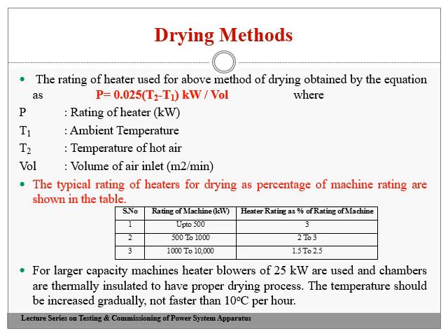Therefore, P equals 0.025 into (T2 minus T1) kilowatt per unit volume, where P is the rating of the heater in kilowatts, T1 is the ambient temperature where you are going to do the drying process, and T2 is the temperature of the hot air that you want. This is the equation from which you can obtain it, once you know the ambient temperature and the hot air temperature you require.